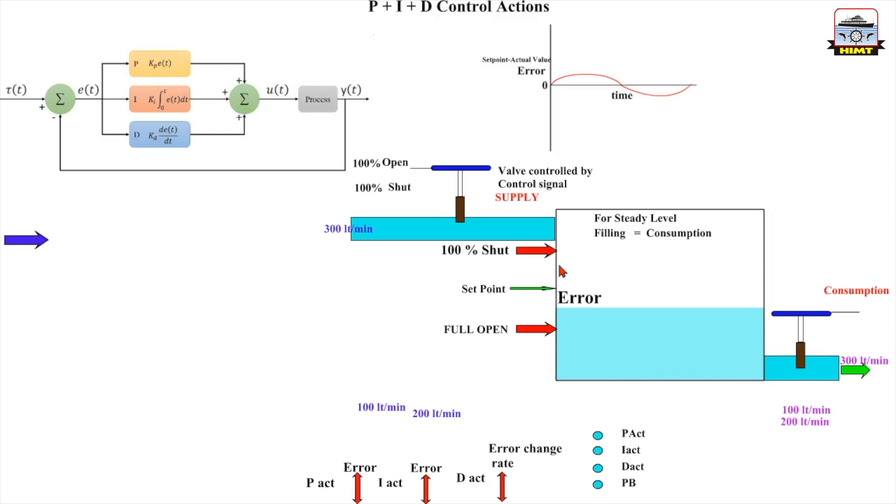Now since the supply is equal to consumption, we call this the steady state condition. Now the level will remain steady here and it will not go down any further. But what we have here left is the error or offset or deviation.